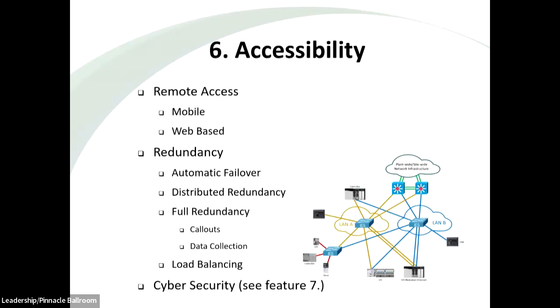Earlier on we mentioned redundancy briefly, and I wanted to dive into this a little more because I think it falls under access. You need to make sure that when you have a primary SCADA server, that server is backed up and you have a redundant backup - maybe even a triple redundancy with a third server sitting somewhere. What's important in redundancy is that if your primary server fails, your backup automatically steps up to take over the functionality of your primary server. We call that automatic failover. It should not require somebody to physically move cables or press a button - it should automatically fail over.